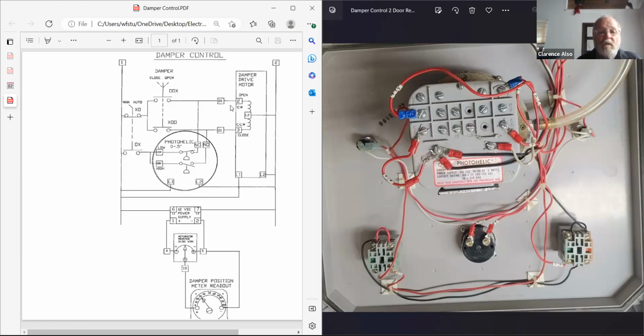The switches are in parallel. This is a spring-loaded switch, and it means that in the middle it's off. We don't want anything happening. Notice that the OOX and XOO, it's OO in the middle, meaning there's not going to be any connection. Then if we go to the top contact, here it says OOX. That means when you spring-load it to open, it's going to put 110 volts across here. It'll go to our terminal number 20, and 2 will get it. We've got 0 at neutral, and it's going to move. And then you let it go, and it's going to go back to the middle.